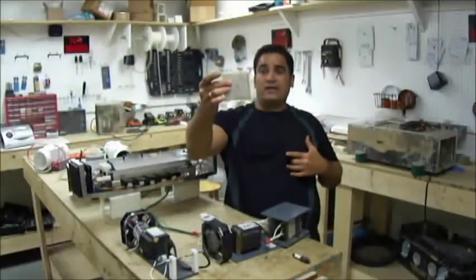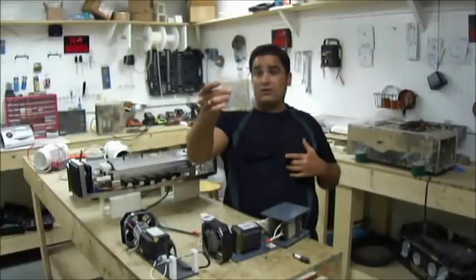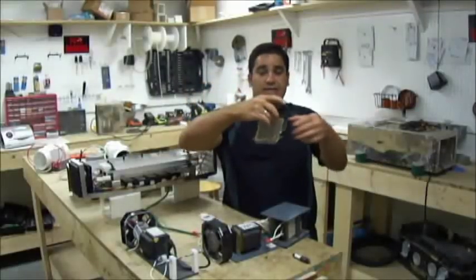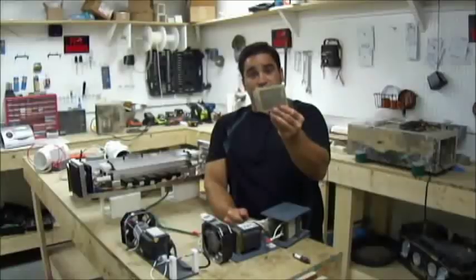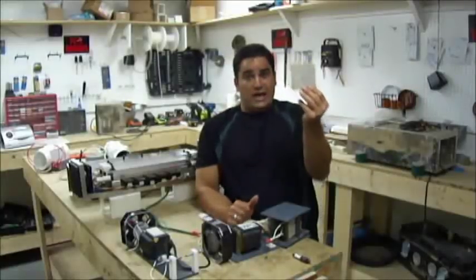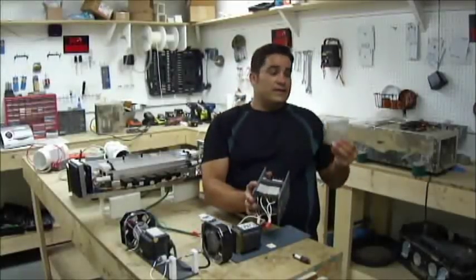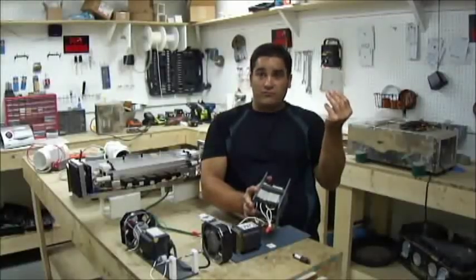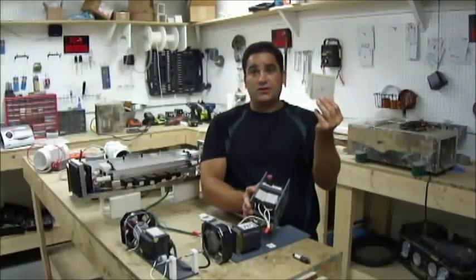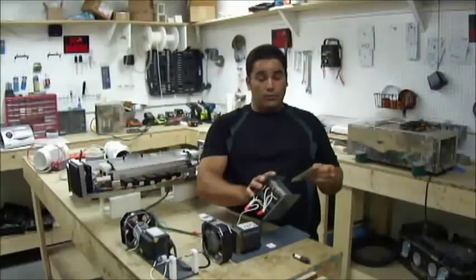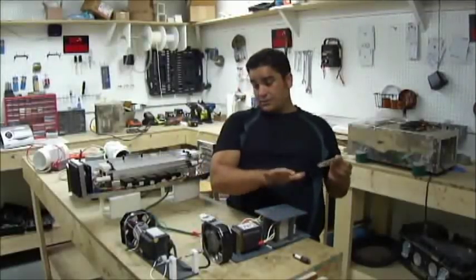This borosilicate glass is a popular thing in low dollar ozone equipment. But as you can see, it is not durable. It's relatively fragile. The benefit of glass over mica is the glass will never burn through. It requires much higher temperatures to create a burn through. Mica will burn through at relatively low temperatures.